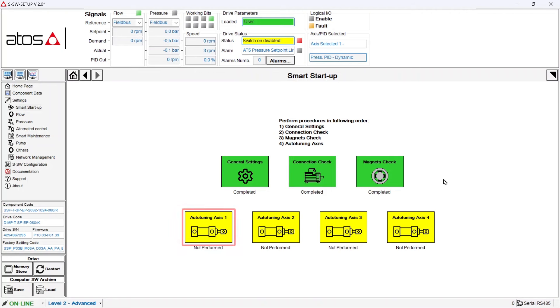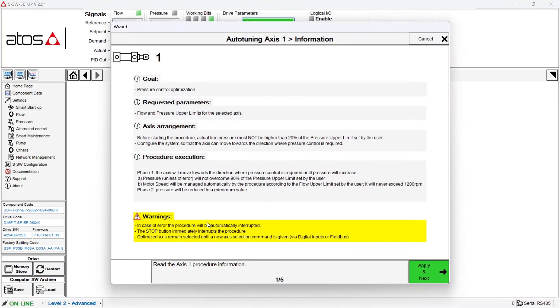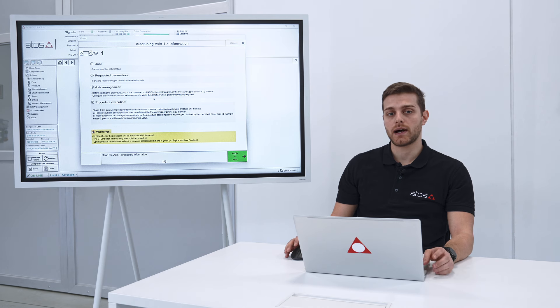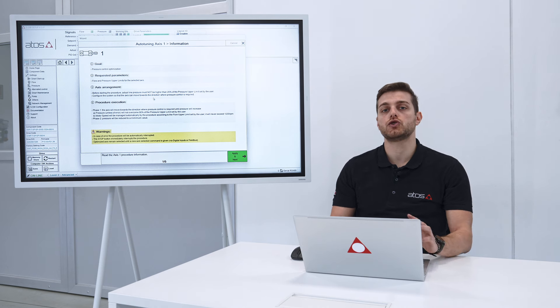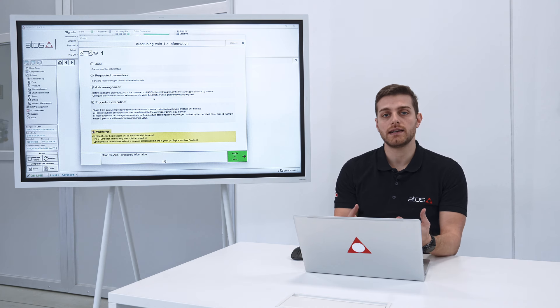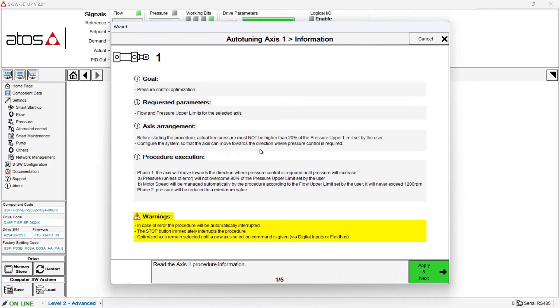Let's go on with the fourth step, axis autotuning. This procedure will perform an automatic optimization of the pressure PID of the servo pump according to the cylinder it's going to move. This optimization depends on your hydraulic cylinder so it must be done directly on your hydraulic circuit.